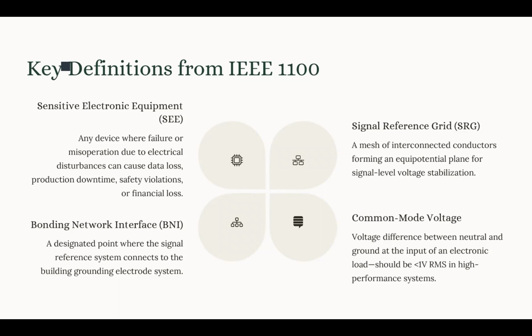Another definition is common mode voltage, which is the voltage difference between the neutral and the ground at the input terminals of the electronic devices. Based on the recommendation of IEEE 1100, it should be less than 1 volt RMS. The reason it's important is that excessive CMV, common mode voltage, injects noise into the digital logic circuits and causes intermittent logic toggling, serial communication errors, or resetting of the power supplies.